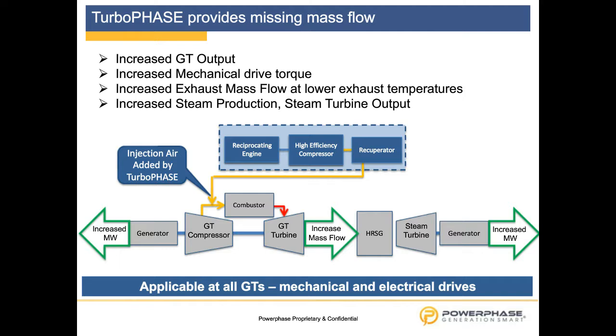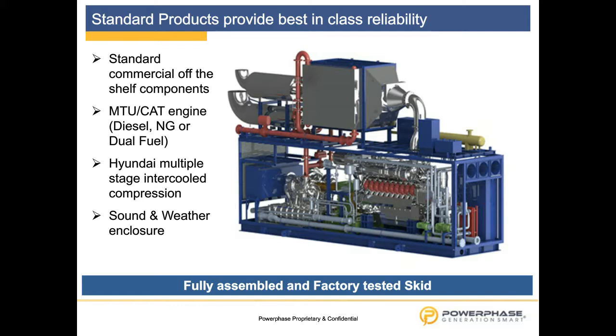So now I want to explain the components itself. What we have here is, in our box, we are using standard components. There's nothing specially produced or manufactured for this particular module. So we use an MTU reciprocating engine. As I mentioned before, we are burning liquid fuel or natural gas. We are dual fuel capable. Then we use a multiple staged intercooled compressor. Everything is comprised into the 40 feet container, and that is a complete factory assembled and tested skid that we just move, completely commissioned and tested, to site, and therefore reduce the commissioning time and the installation time to an absolute minimum.